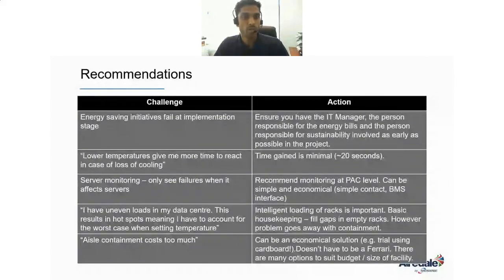Second point, lower temperature gives me more time to react in case of loss of cooling. So this is not very correct, because even if you set it at 26 degrees Celsius, or even if you set it at 22 degrees Celsius, given the amount of kilowatts, or the heat generated in a data center during the downtime, it quickly increases the heat. So that point is not very much valid.